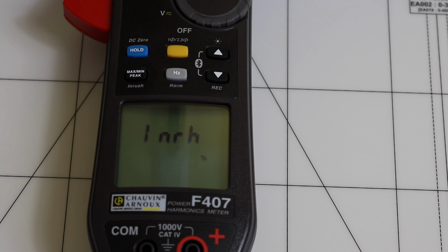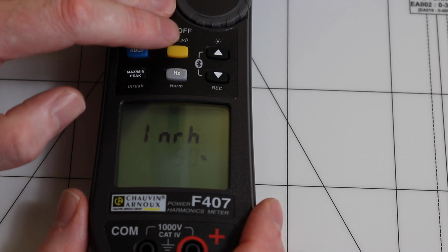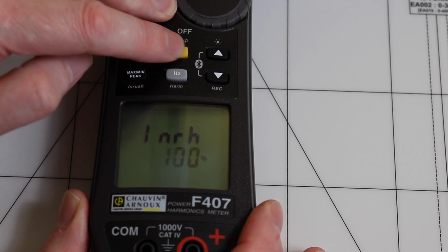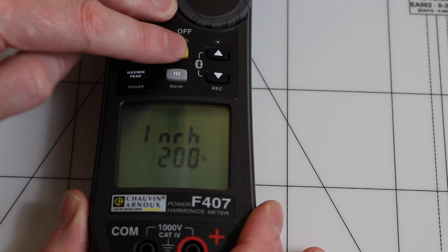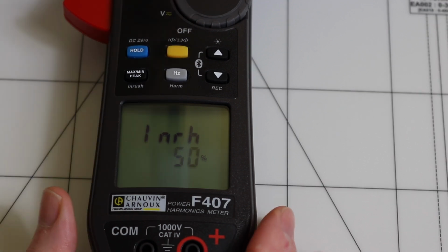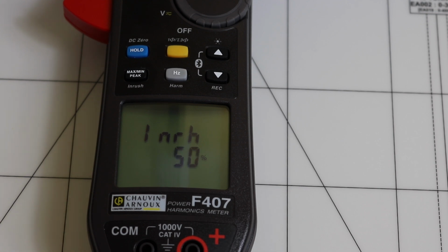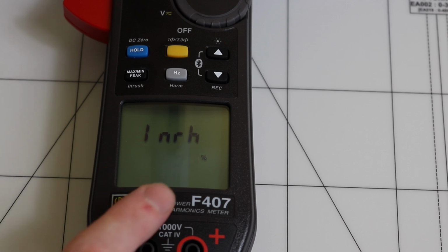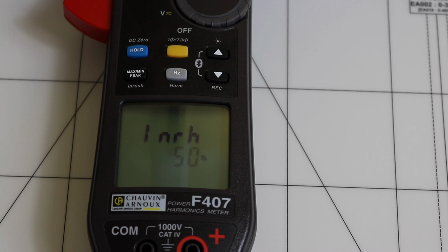This is a bunch of fixed options that you page through using the yellow button up here. Get to 70%, 100%, 150, 200, and then round to 5, 10, and then we're back up to 50 again. So that percentage value that you're seeing there is an increase on the current that the instrument is reading. So if your instrument is reading at 100 amps, the threshold would then be set to 150 amps. So it does work slightly differently to the usual inrush function you see on these clamp meters.